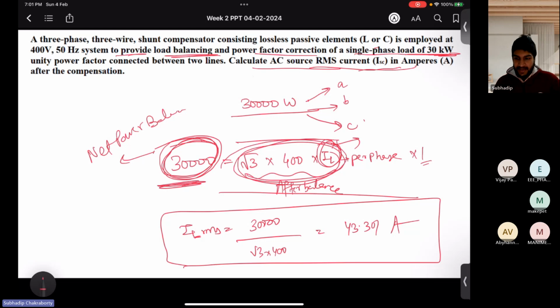Net 3-phase power, or any power, single phase or whatever, the net loading needs to be the same before and after compensation, because remember, compensators don't draw any active power. They are only used for mitigating, that is, balancing and power factor correction, and for negative sequence components. They don't themselves draw any active power. So that's why, for the single phase loading of 30 kilowatt, after providing compensation and making it balanced, the current will be 43.301.